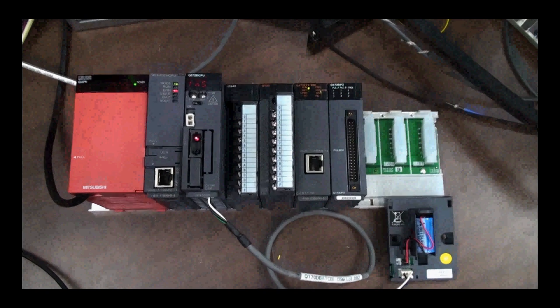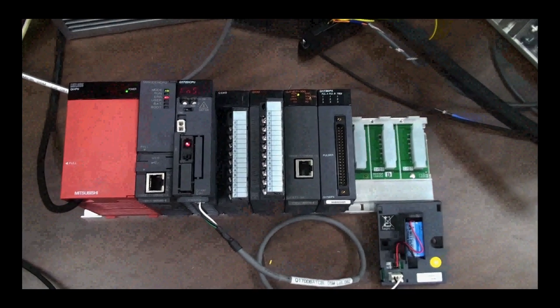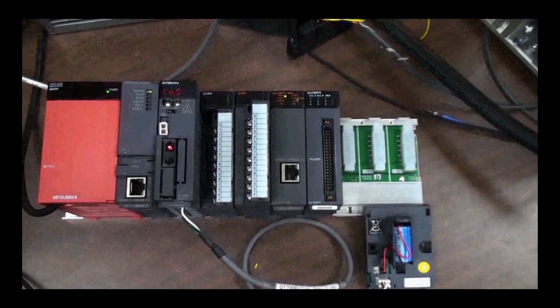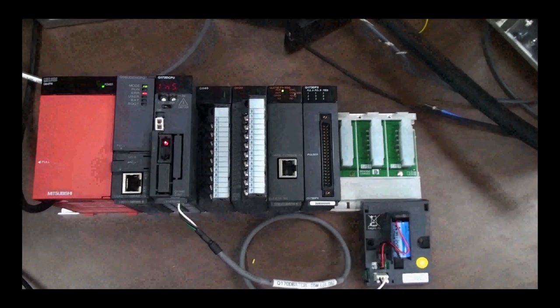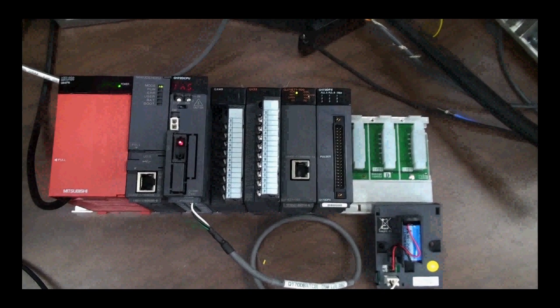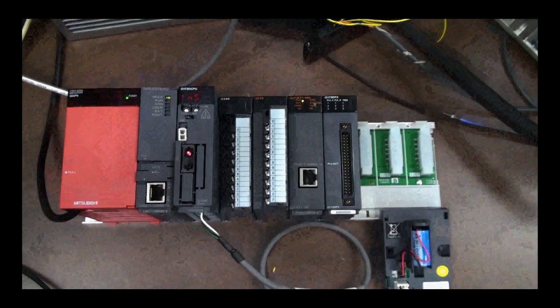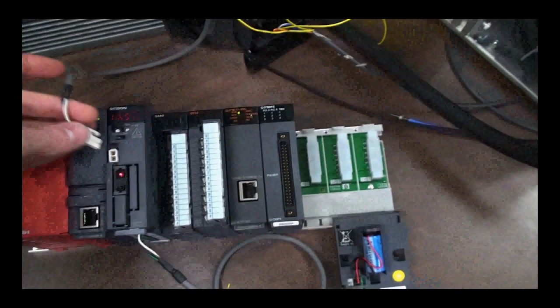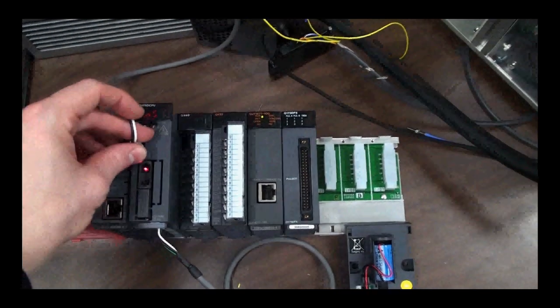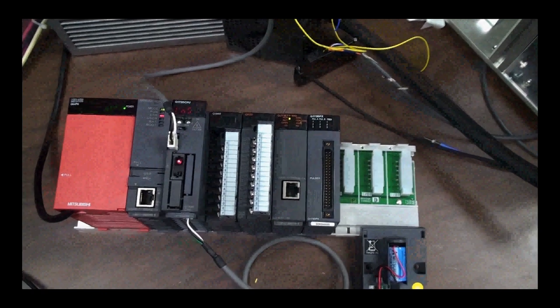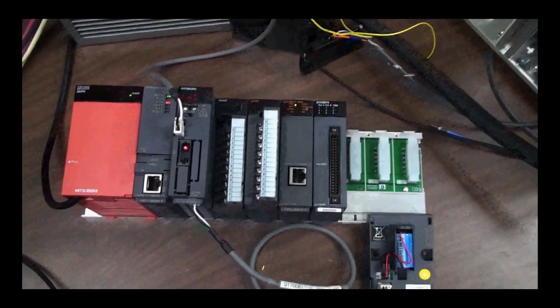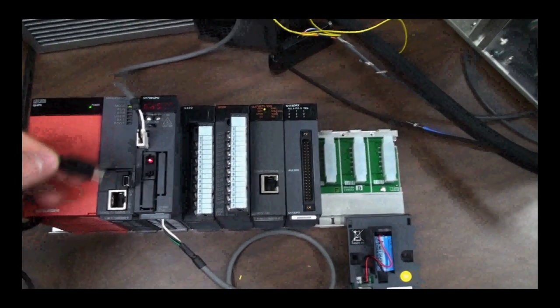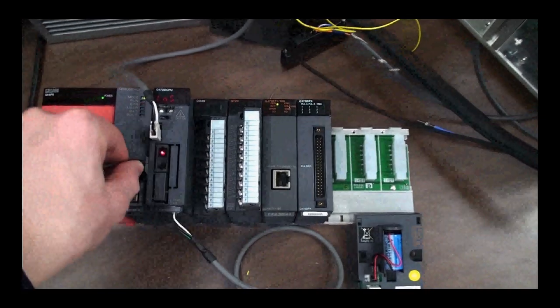And so now going back to our rack you can see that we have the motion controller with an INS display. That means it's in install OS mode. That means we need to install an OS before we can go any further. First of all it's a good idea to connect an EMI cable for the force stop on the controller. This is new for the IQ based motion controller so you can connect 24 volts to the motion controller now if you wish. Next thing you're going to want to do is plug in a USB cable to program the motion controller through the PLC.